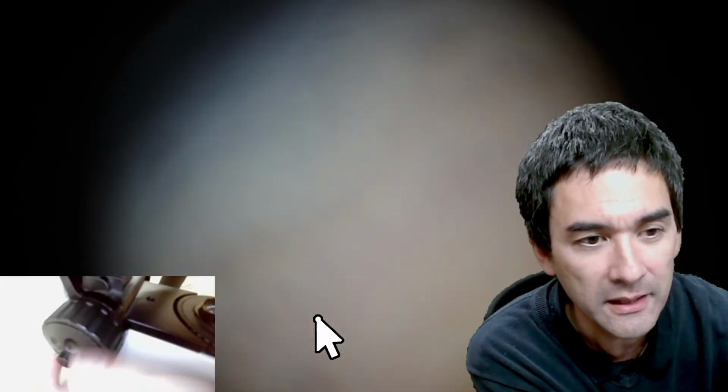So what I can do is, when I've got everything in focus, okay, everything is in focus, I will lock it. I will lower everything, so I will lower the stage. I will put my drop of oil on the slide, and then I will go up again, and it will simply lock on this position, and it's going to be in focus. So there is no risk for me crashing the objective into the slide.